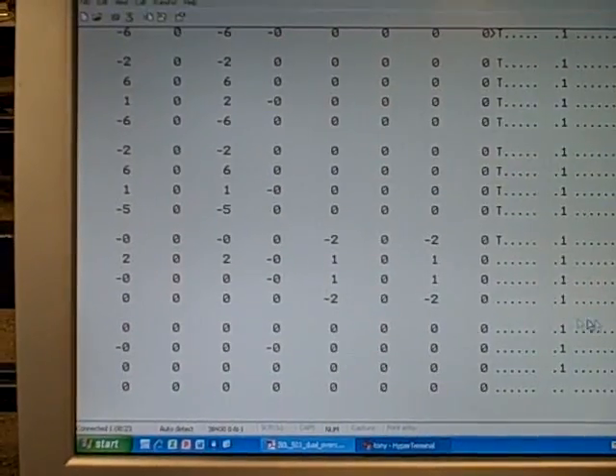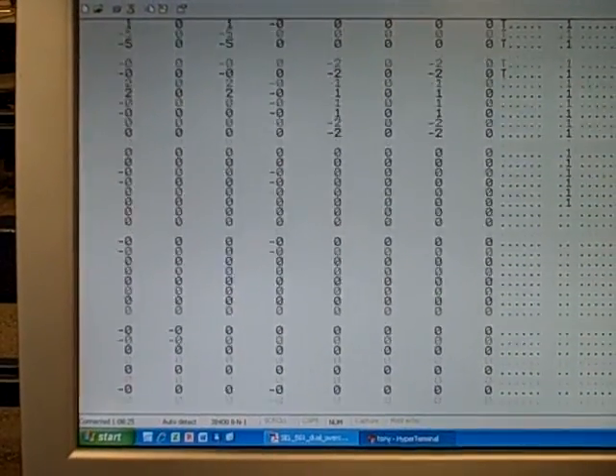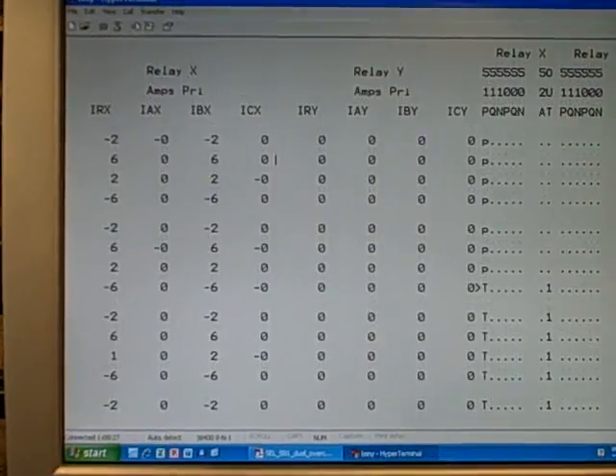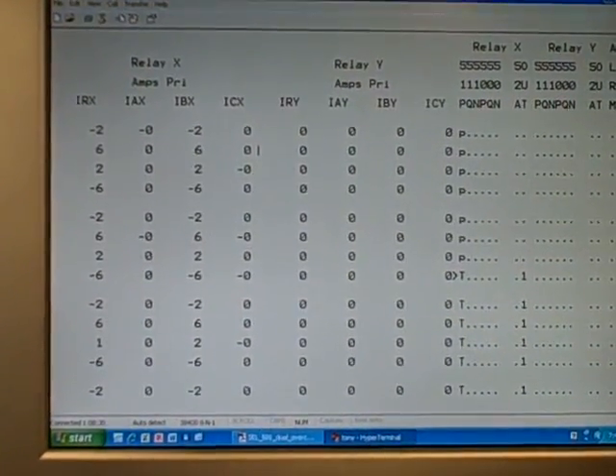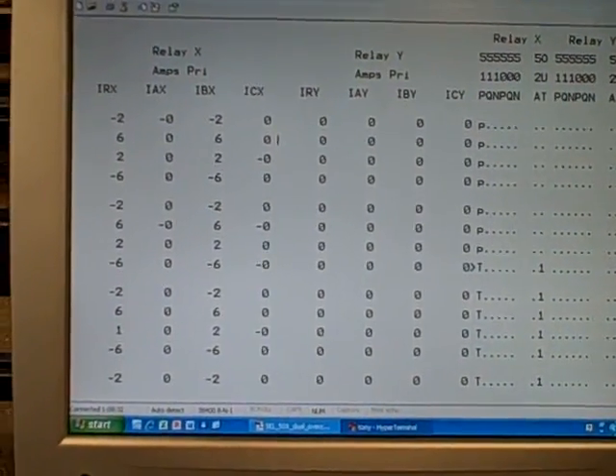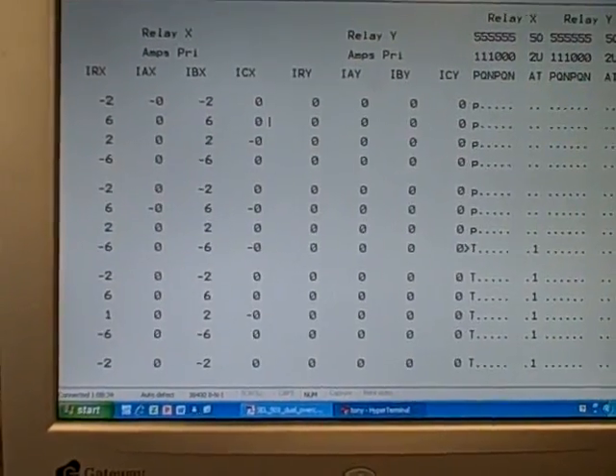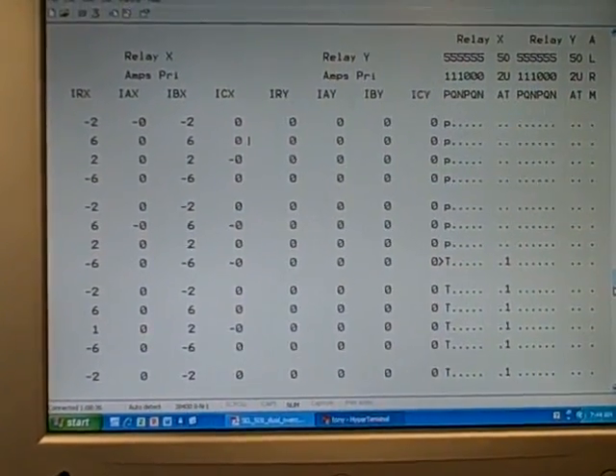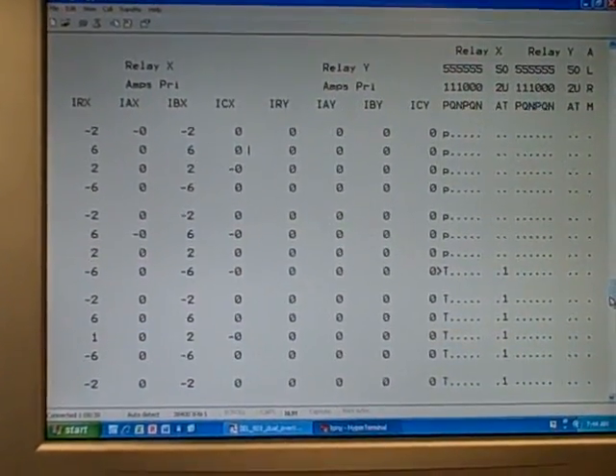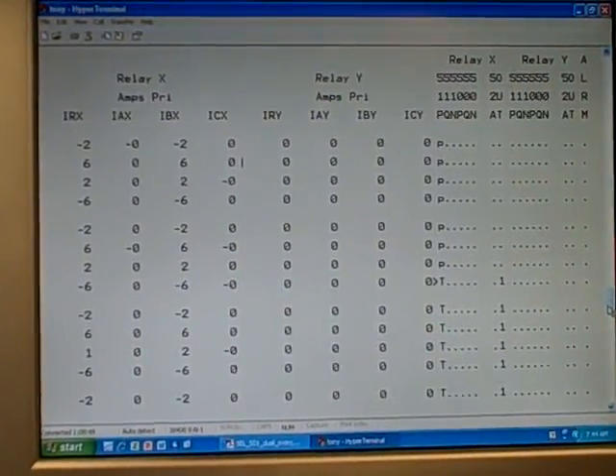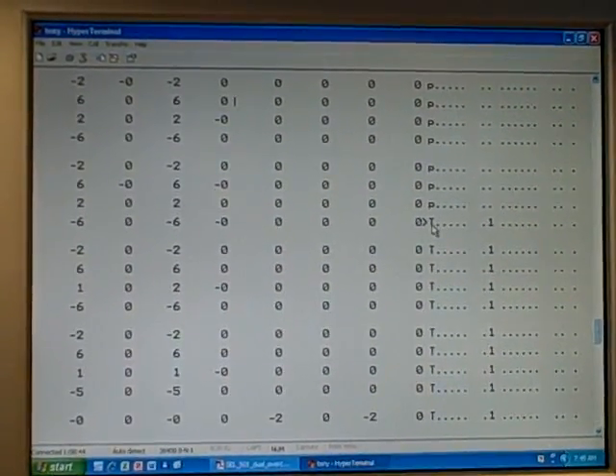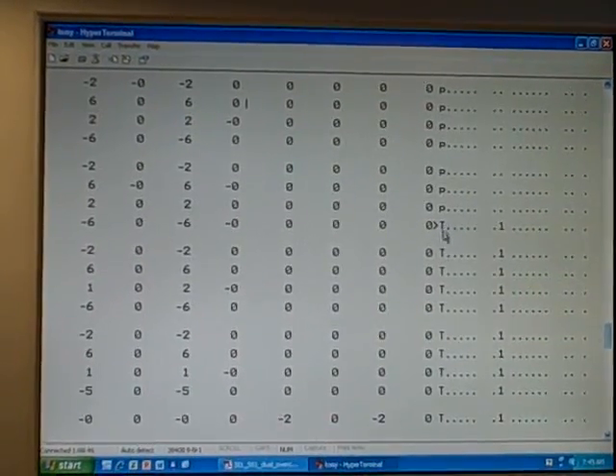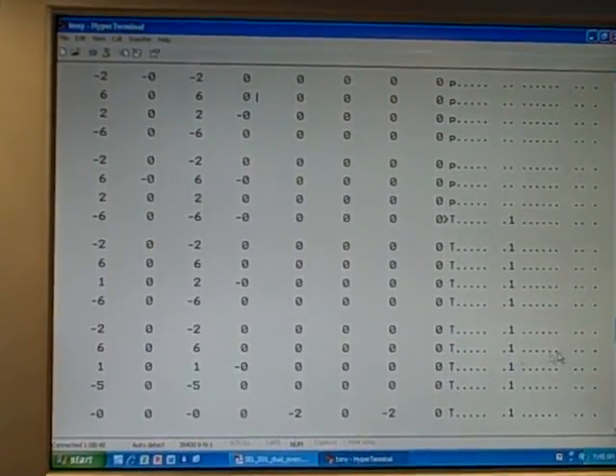And then down here, you see zero current through phase B. So this particular relay has recorded 15 cycles worth of event history. And of course, it cannot start at the very beginning of the event when I turned on the vacuum cleaner, because from there to the trip was much longer than 15 cycles worth of time. So what it did is it showed me a snapshot where the trip event happened fairly early on in the 15 cycle history, and then I can see what happened afterwards.